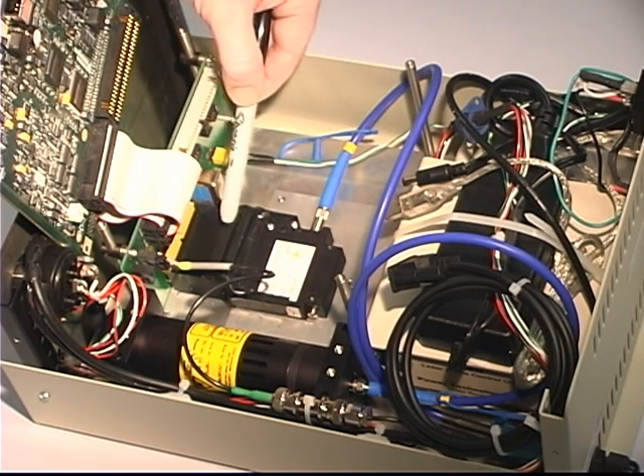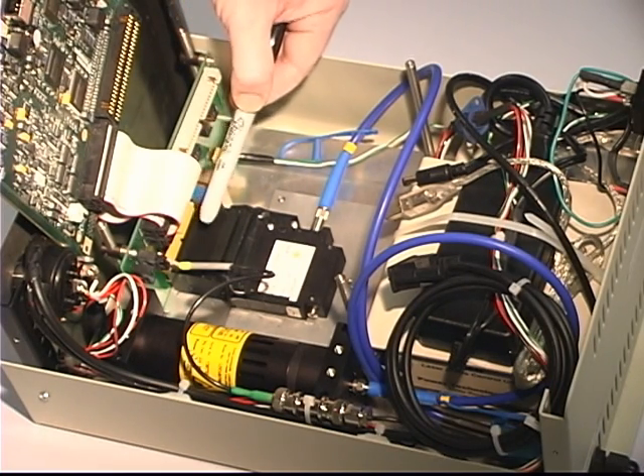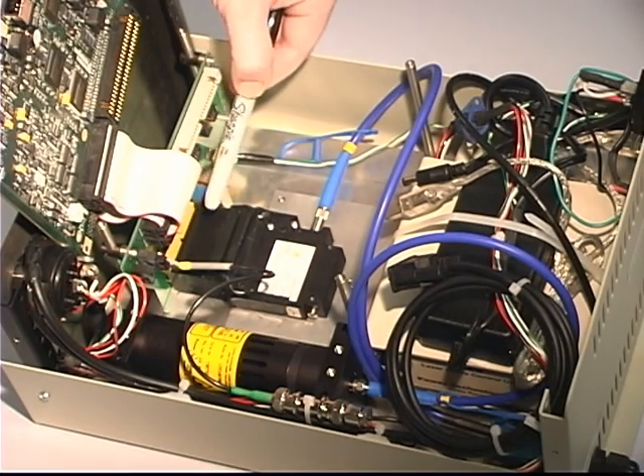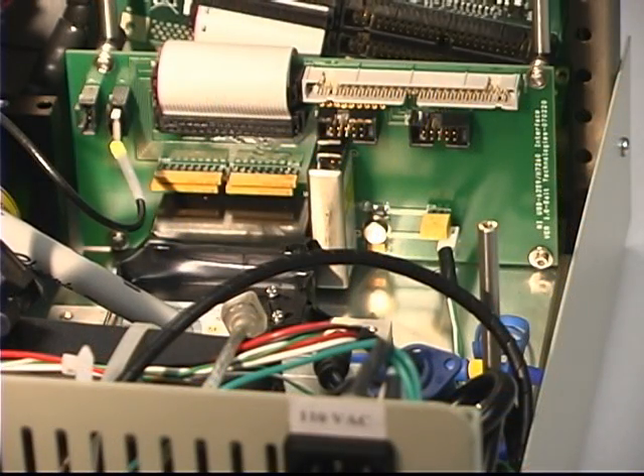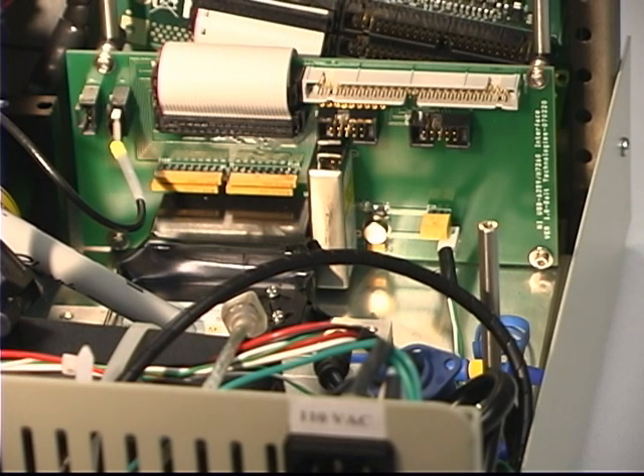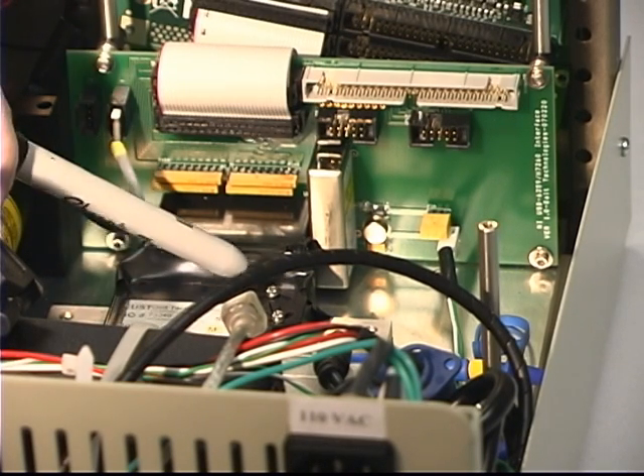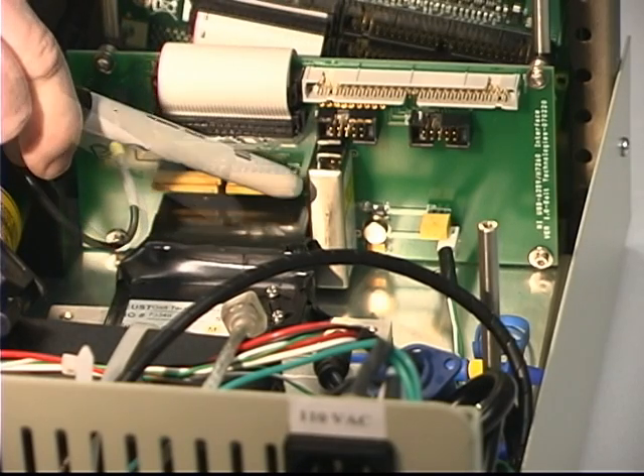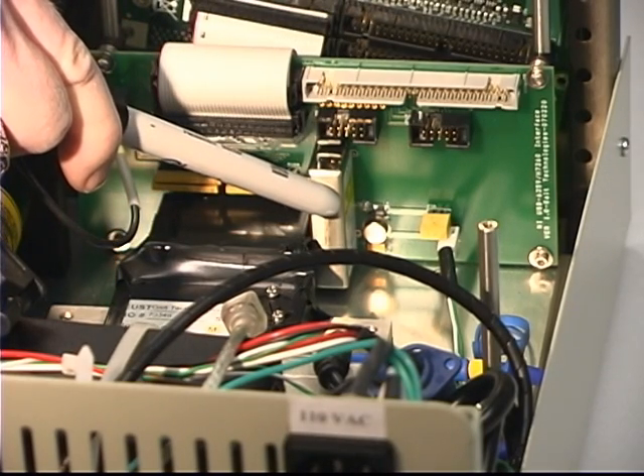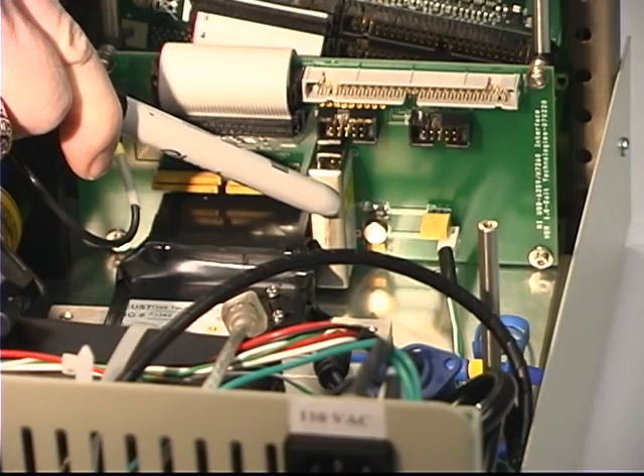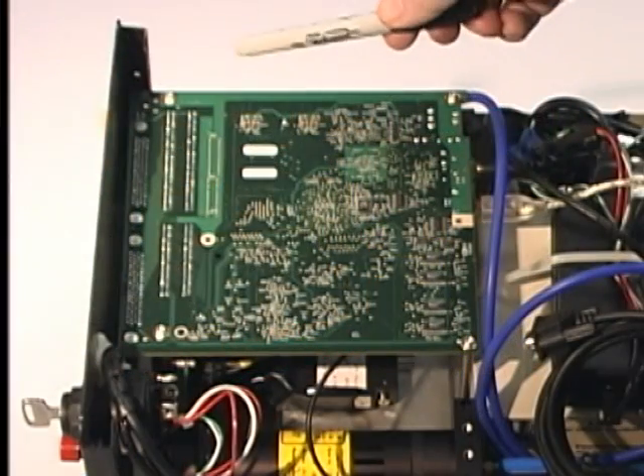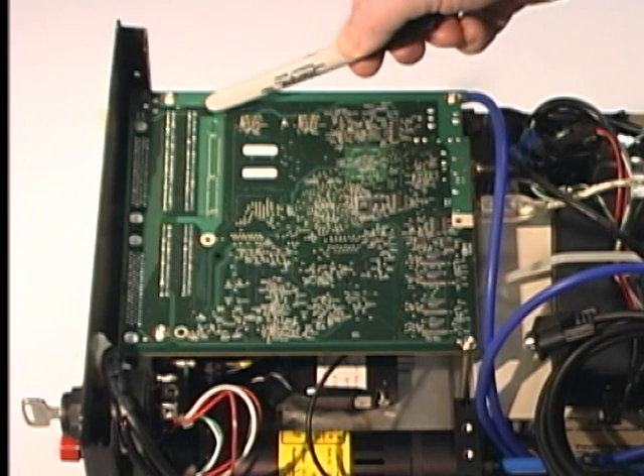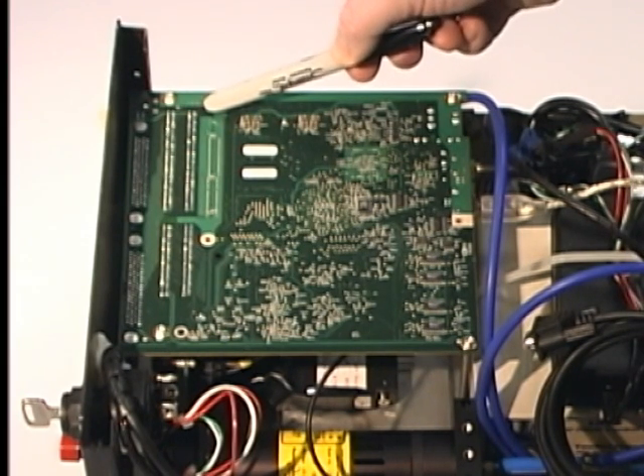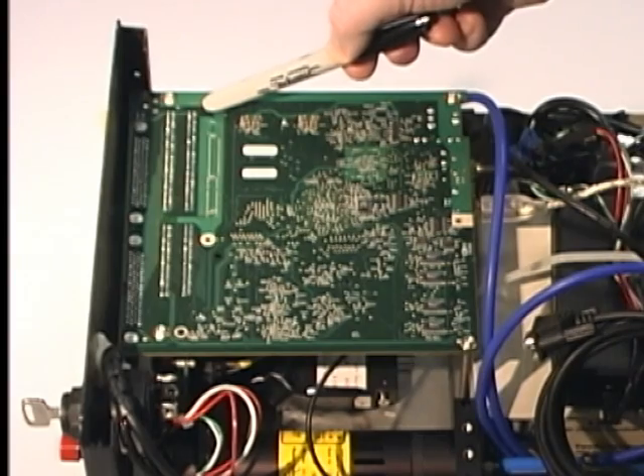An optical filter is used to reject backscattered laser light that makes its way from the sample surface to the spectrometer. The PMT and optical filter are located on a custom detector board. Laser-induced fluorescence emission exiting the spectrometer is detected by the PMT and converted to voltage by shunt resistors located on the detector board. A high-voltage power supply, also located on the board, provides high voltage levels required for operating the PMT. Low-level voltages required as input to the detector board are provided by a DAC channel on the analog-to-digital converter and are controlled via software.